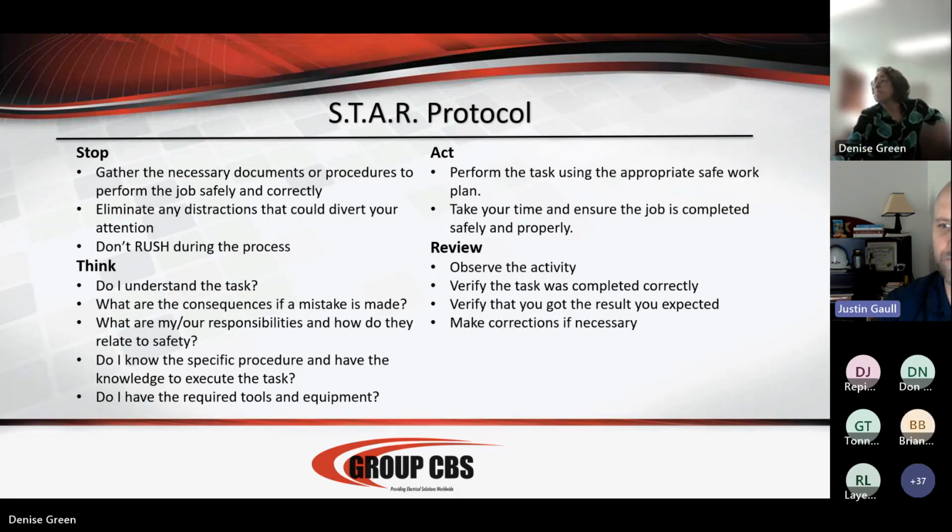Denise asks, what do you consider monitoring equipment? So I know AEMC makes one, like flexible CTs and voltage clips to have maybe a recorder, and say, hey, we think we're using more amps than we've anticipated, or can we add another circuit to this motor control center, or are we already at the max, but we really don't know if we're at the max because there's no metering, there's no anything. That's what they mean by monitoring equipment. So temporary equipment to check a circuit or monitor a situation.